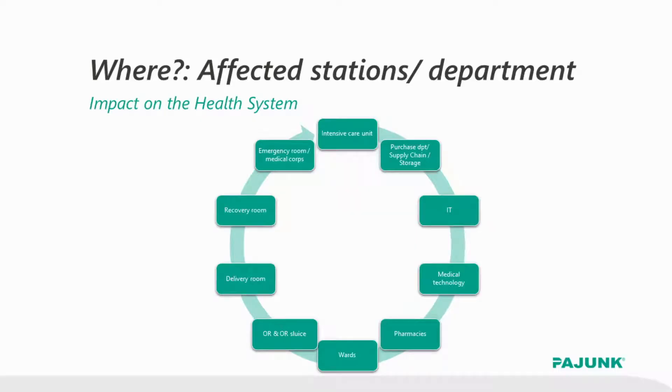This brings us to one of the biggest challenges of ENFit conversions. It is very important to define all departments that are affected by such a conversion and all personnel and staff that need to be involved during the process. By now it should be very clear that ENFit is not just a topic for purchasing or sourcing departments. For example, if syringes are prefilled with drugs in the hospital, the hospital pharmacy could also be affected. Do the ENFit syringes fit with the compounding or filling machines?